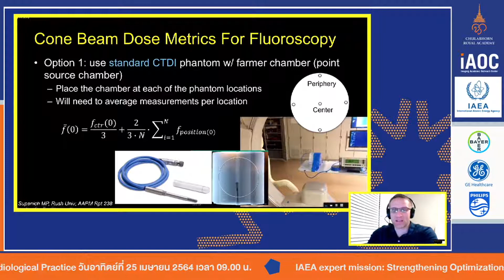In one case, they looked at using a very long phantom, 600 millimeter phantom. It actually comes in 3 chunks. The thing weighs, I'd say, probably getting up close to 70, 80 pounds when you heft that thing around. So it's not for the faint of heart if you're lugging this thing around. It's got a center hole, and it's got a couple other holes, one at the periphery, and then a couple of holes, not necessarily at the periphery, but kind of intermediate.